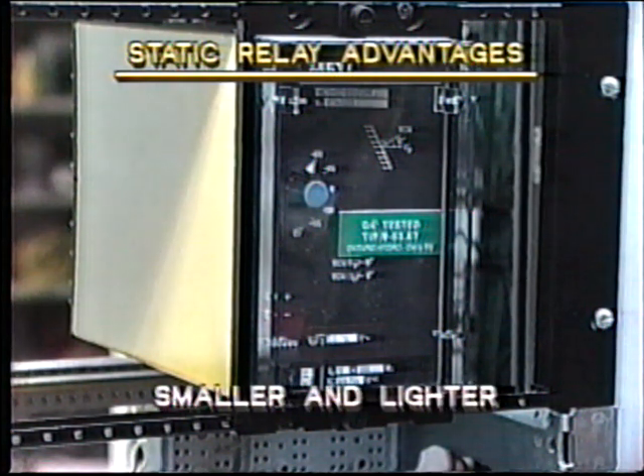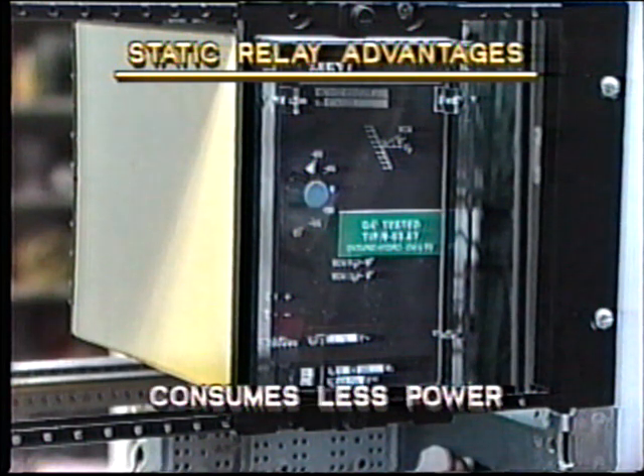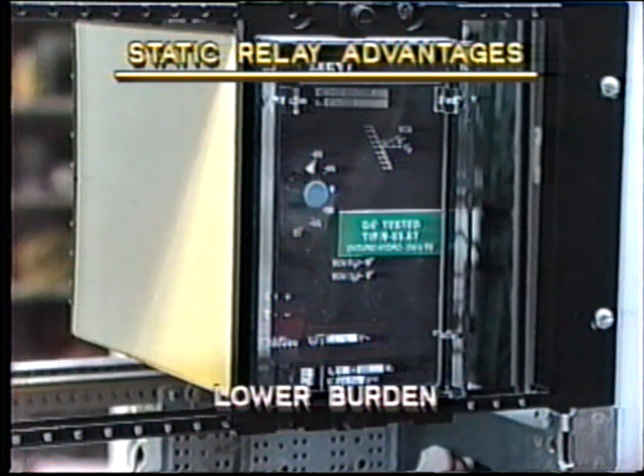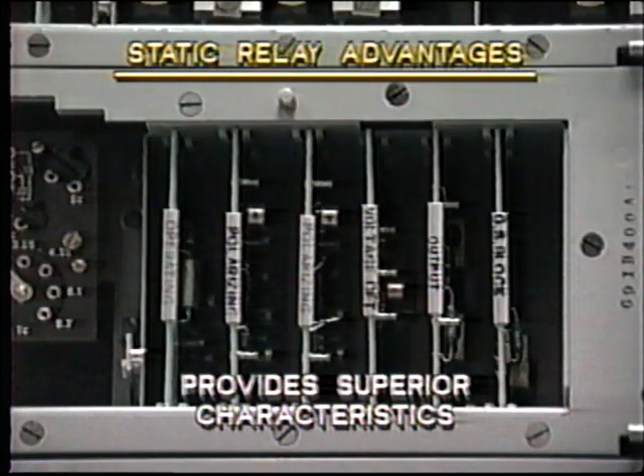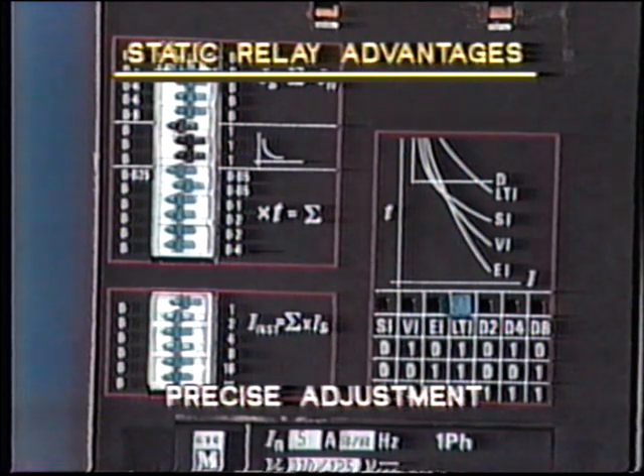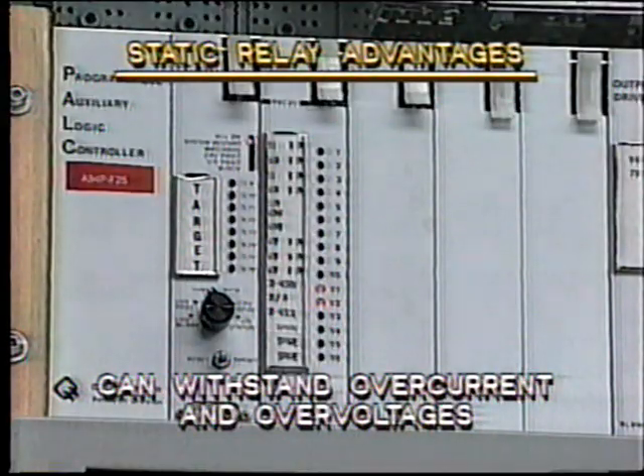It is much smaller and lighter. It consumes far less power in operation. It presents a much lower burden to the CTs and VTs. Its circuitry can be arranged to provide similar and even superior characteristics to equivalent electromechanical relays. The relay reset value can be adjusted more precisely due to the lack of mechanical inertia and overshoot. It has the ability to withstand overcurrent and overvoltages for longer periods of time.